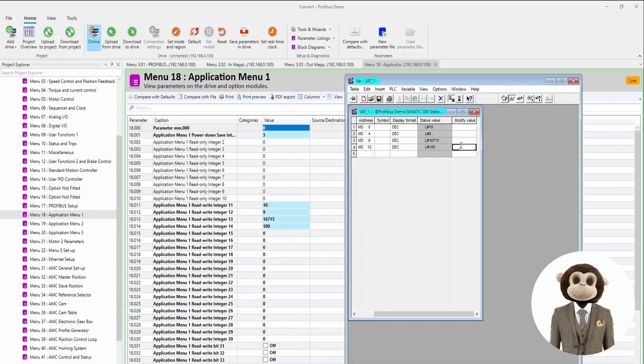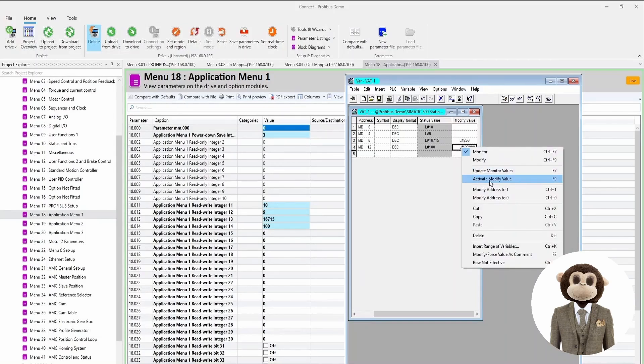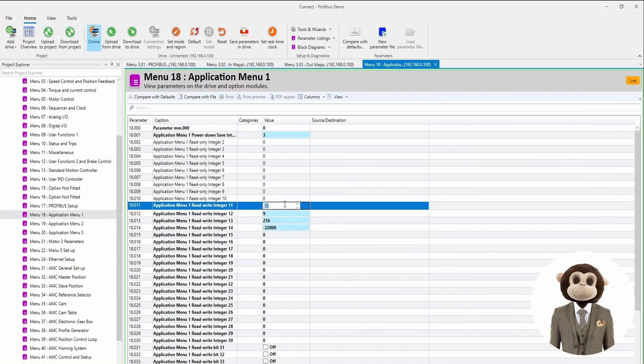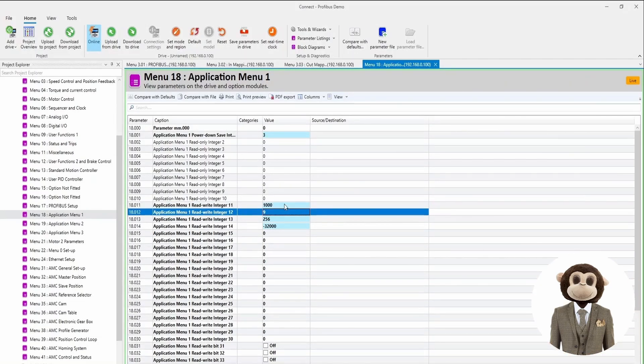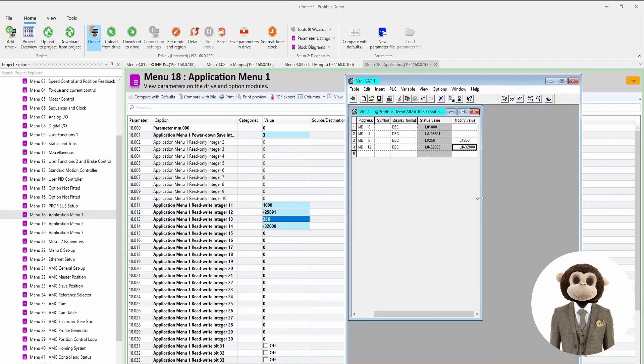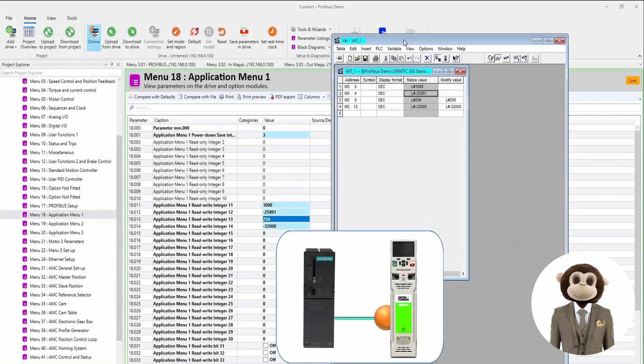If we modify these values and activate the modify value, we can see the values update in the drive. If we change the values in 18.11 and 18.12 and look at the variable table, we can see the values being read match what we wrote in the drive. This demonstrates the complete setup for PROFIBUS cyclic communication between the M700 and the S7-300 Siemens PLC.